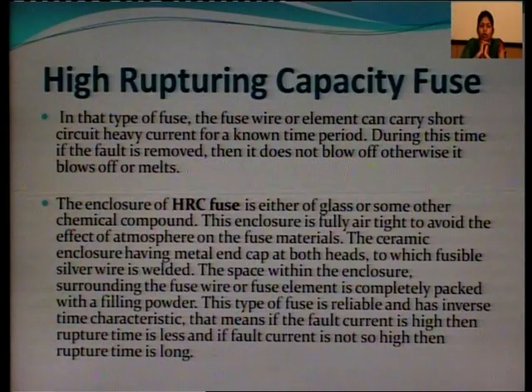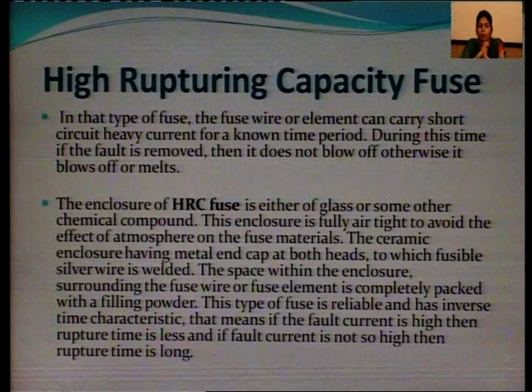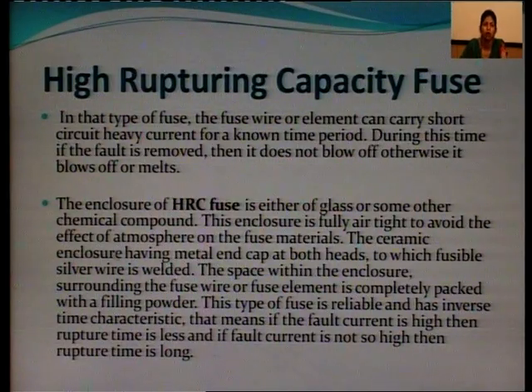The enclosure of the HRC fuse is either glass or some other chemical compound. This enclosure is fully airtight to avoid the effect of atmosphere on the fuse materials. The ceramic enclosure has a metal end cap at both ends, to which fusible silver wire is welded. The space within the enclosure surrounding the fuse wire or fuse element is completely packed with filling powder.